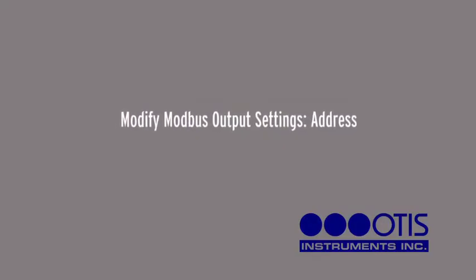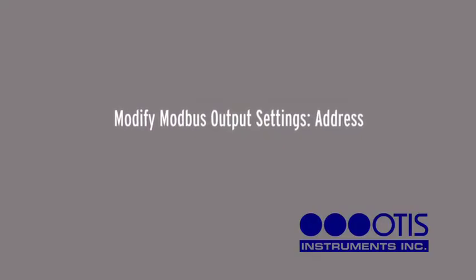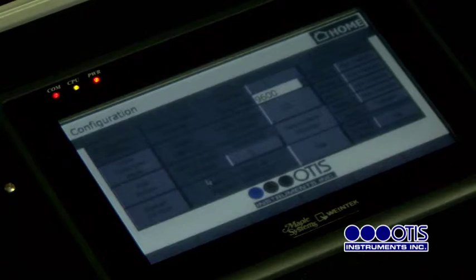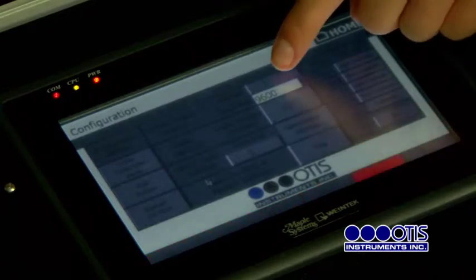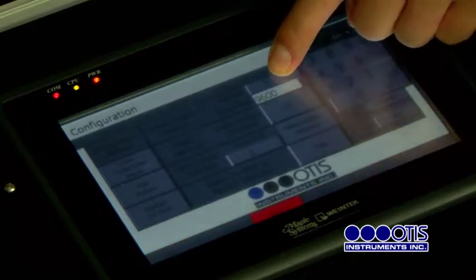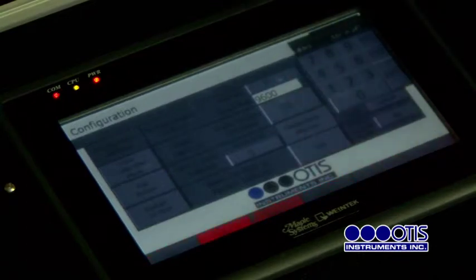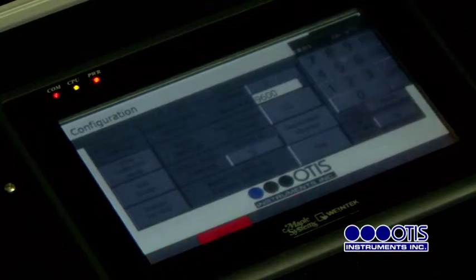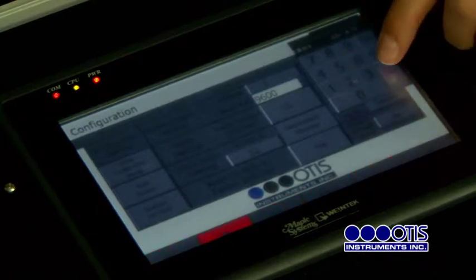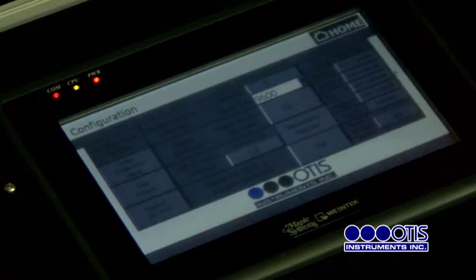Modify Modbus Output Settings — Address. While in the second level configuration menu, modify the address by touching the number next to the word Address. When the numeric keypad appears, type the desired address number and then press ENT.